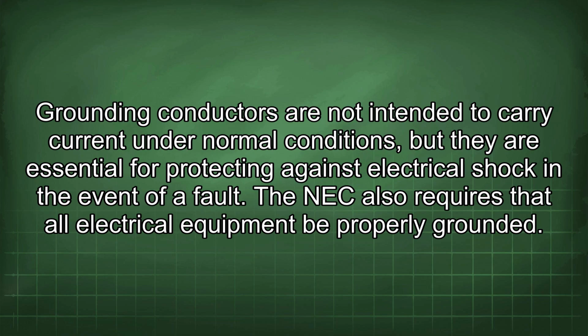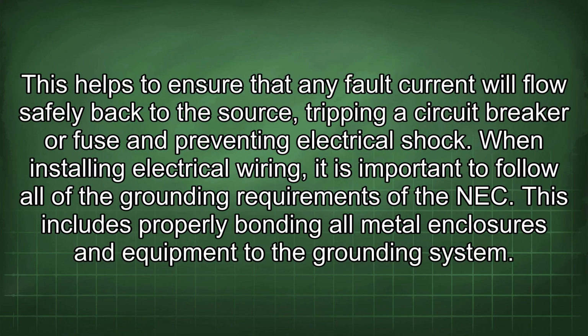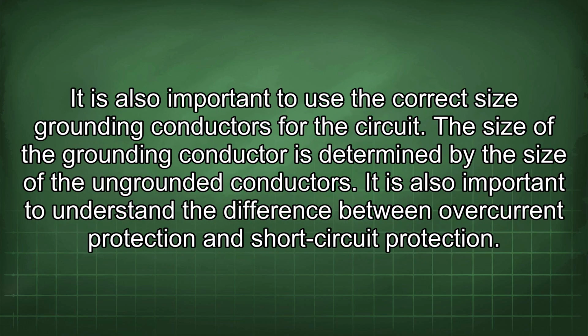The NEC also requires that all electrical equipment be properly grounded. This helps to ensure that any fault current will flow safely back to the source, tripping a circuit breaker or fuse and preventing electrical shock. When installing electrical wiring, it is important to follow all of the grounding requirements of the NEC. This includes properly bonding all metal enclosures and equipment to the grounding system. It is also important to use the correct size grounding conductors for the circuit. The size of the grounding conductor is determined by the size of the ungrounded conductors.